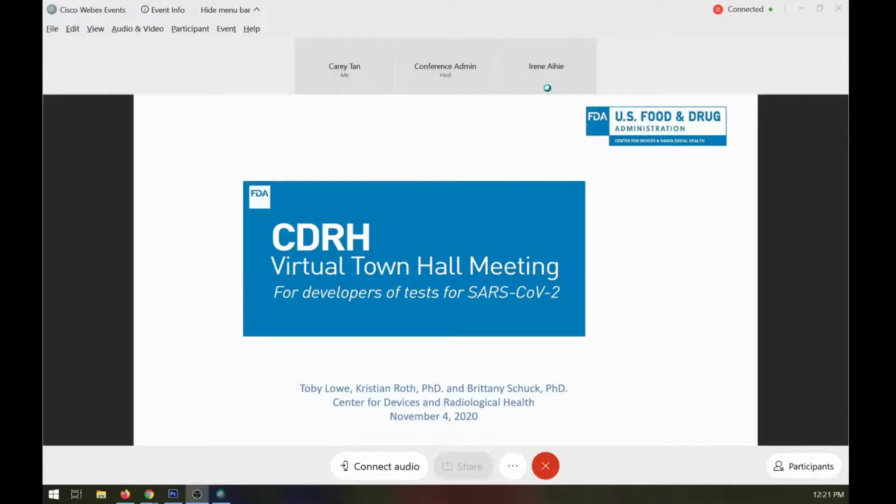But we would expect the saliva collection to be done with a legally marketed saliva collection device. The collection device otherwise would need to come in for authorization if it's not one that is already authorized. Right. Okay. And it doesn't have to be standalone. It could be part of another test kit. Can you clarify that? Some test kits have the collection device built into that EUA, and some collection devices have an EUA just as a standalone. Right. If a collection device is included within an EUA for an assay, then that collection device is only authorized for use with that assay. In order for a collection device to be more broadly legally marketed, it has to have that standalone authorization. Okay. All right. That answers it.